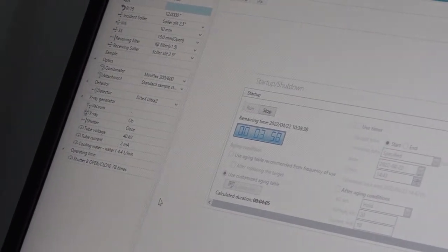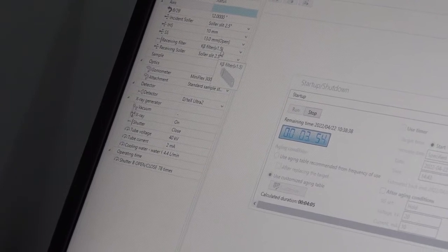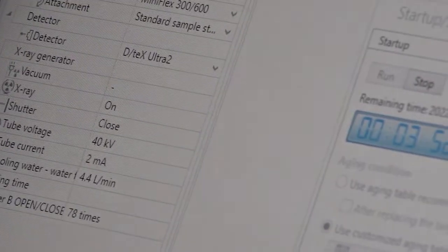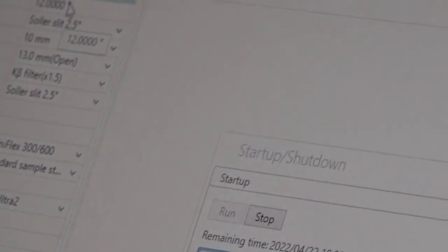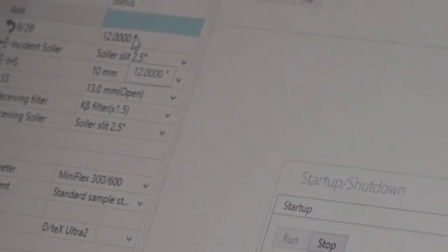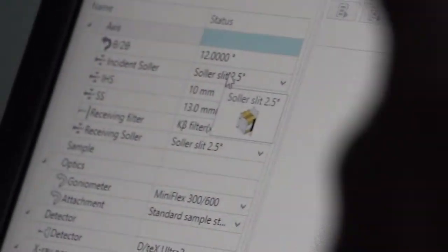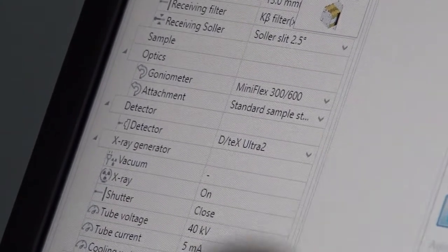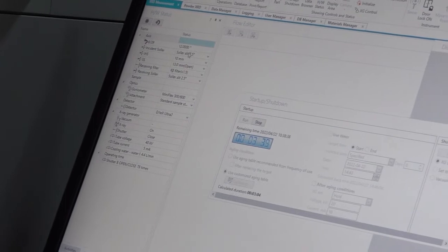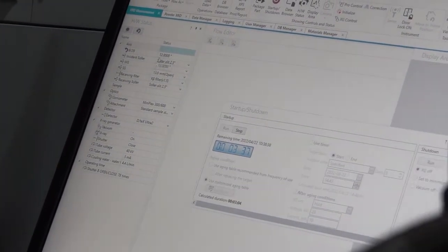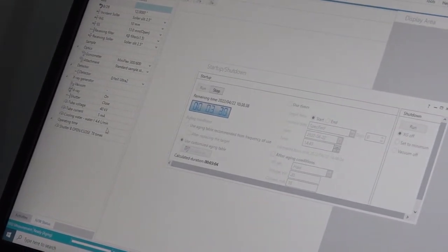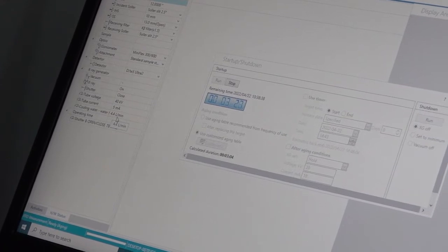How do you customize the slit size? That is default now, madam. Normally we are using only these slits, but it depends on your sample. See, I told you, the divergence slit is now 10 mm. If your sample is very small, you can use 5 mm, 2 mm like that. So that can be customized, yes, before we run. And you can see the chiller flow is there, 4.4 liters per minute. If it goes less than 2.5, the X-ray will trip.